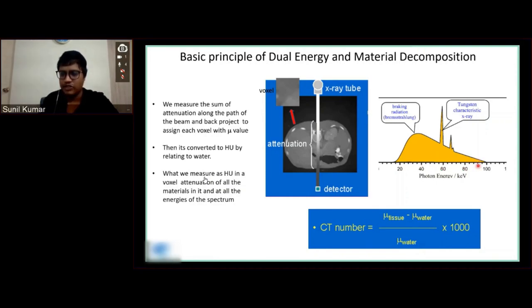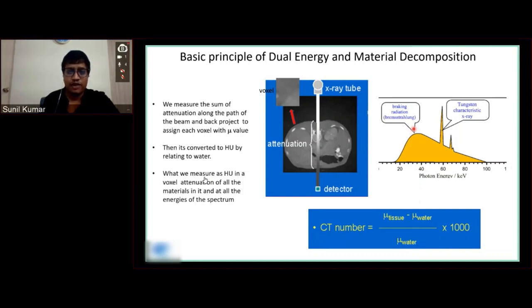Keeping this in mind, we understand that radiation is of a polychromatic energy. There's not only a single energy for an individual tissue; instead, we have a variety of energy ranges for one particular tissue. So when that is assigned to a voxel, it will give us an average HU value of that particular tissue, rather than the single element inside the tissue.